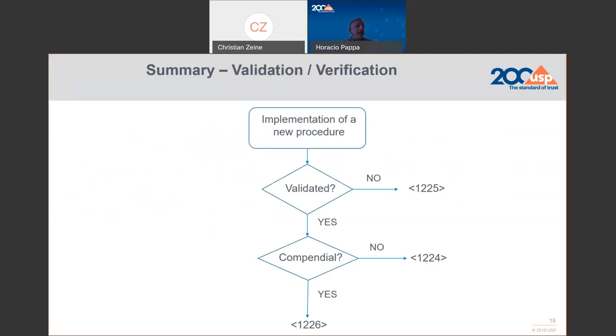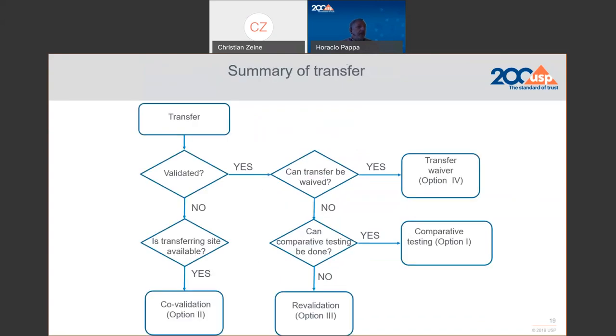Briefly, how we define when to use validation versus verification: when the method we are trying to implement is not validated, we will validate using 1225. If it is validated and it's a compendial method, we will use verification under 1226. If it is validated but not a compendial method, the appropriate activity will be transfer.